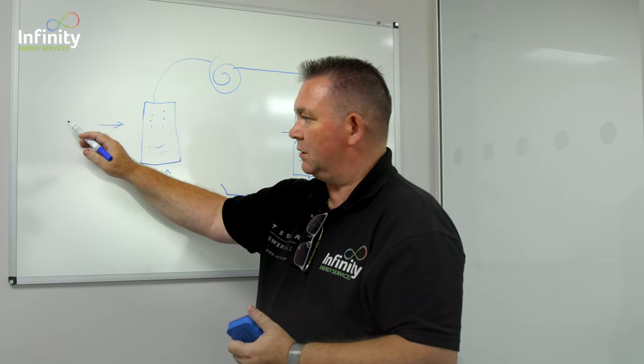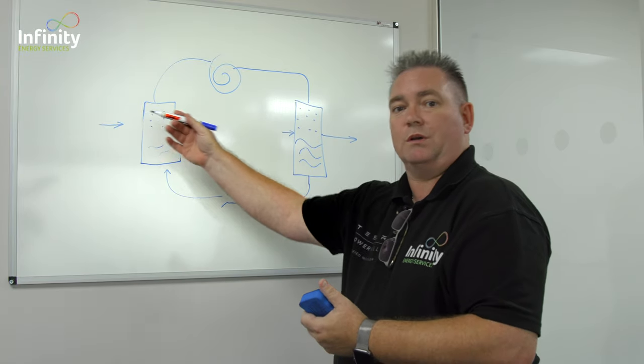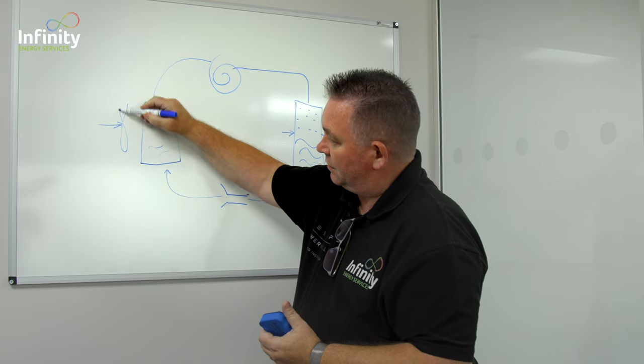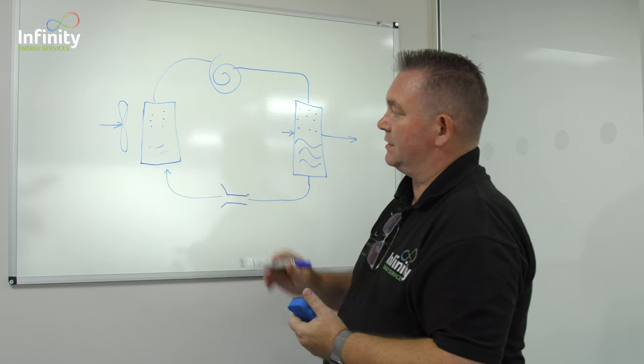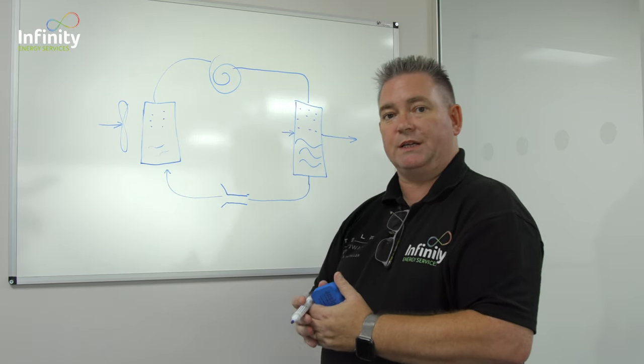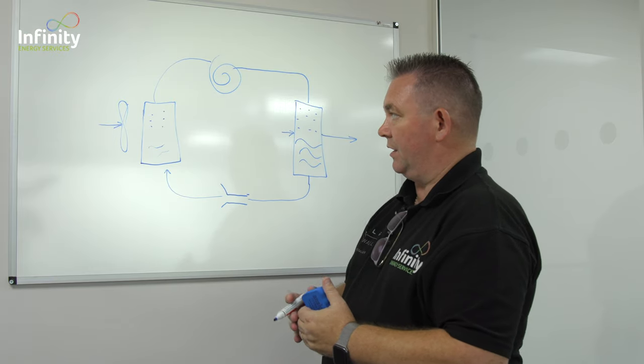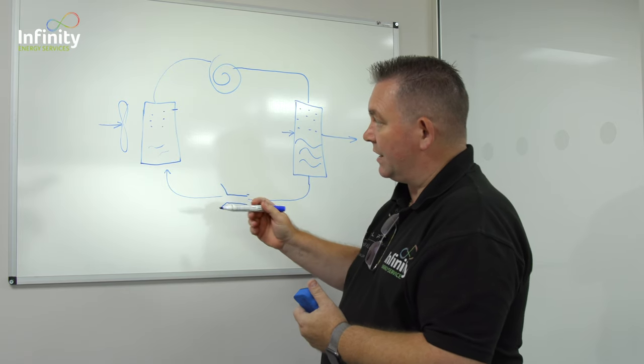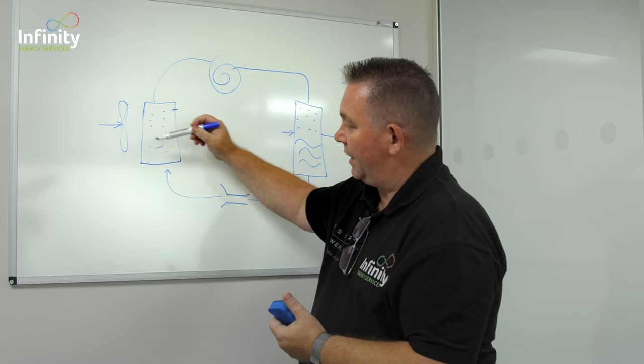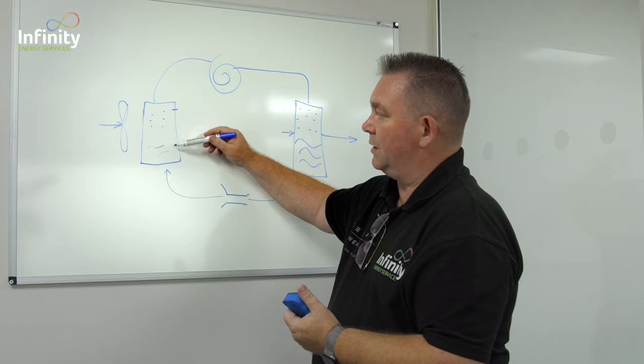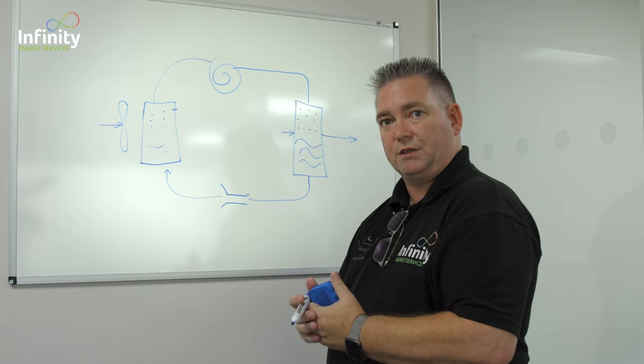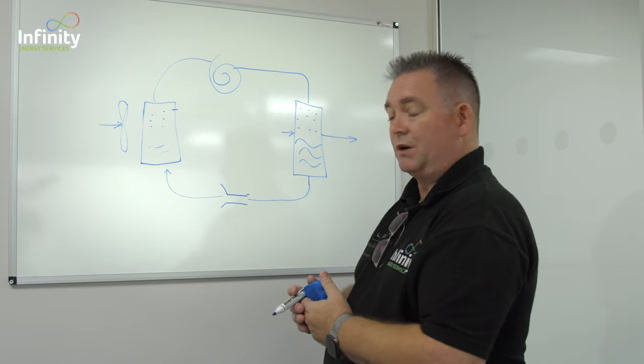So we don't need loads and loads of air and temperature coming across one side. The fan which is running the air across heat exchanger will be modulating and it modulates depending on what temperature this is up here and what state it's in. As long as we can take enough energy out of the air to change the phase from a liquid to a gas we can load that gas with energy with the compressor.